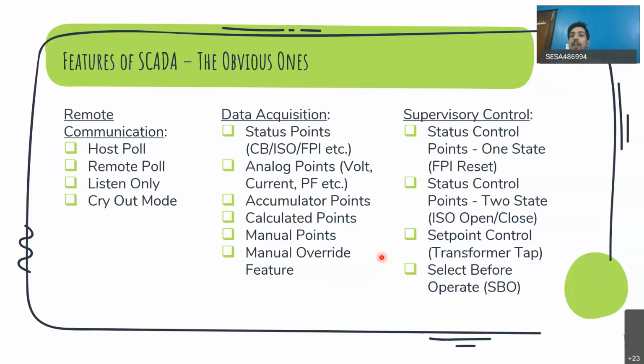So you can control single state devices like your fault passage indicators. So generally fault passage indicators will be in either set state or reset state. Set will be automatically done when fault current passes through. You cannot set an FPI. So you can only reset an FPI. So that is single state points you can control. You can control two state points like opening or closing an isolator, etc. You can control set points like transformer taps. Current position is tap position 2. You can change it to either 5 or -2 or whatever.